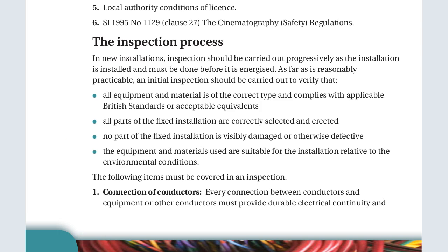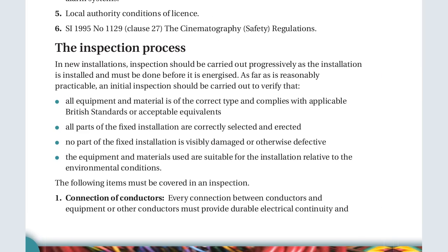Now, the next thing we are going to do is look at the process of inspection. We have already finished installing. We have the equipment. We know what is needed. We know what to expect. Now we are going to go through the process of inspection. What are these steps? In a new installation, inspection should be carried out progressively as the installation is installed, and must be done before it is energized. Normally, inspection is done before a house is energized. For example, if you are doing an installation for a new build house, or an extension of a house, you have to inspect before you can power that house.